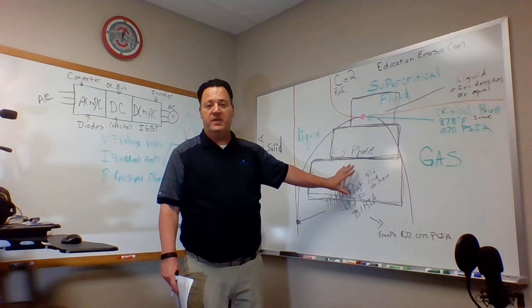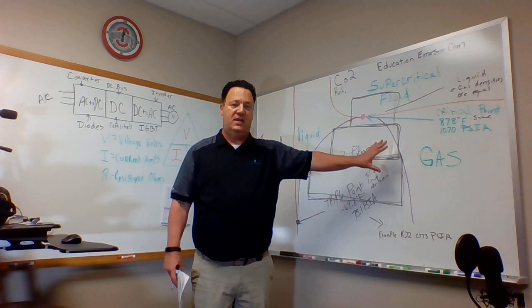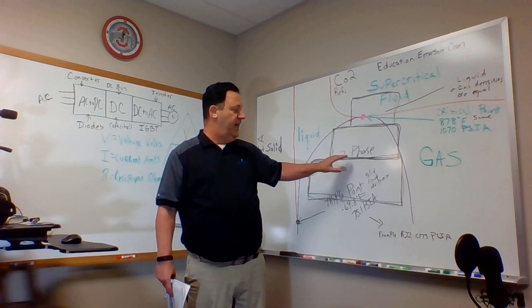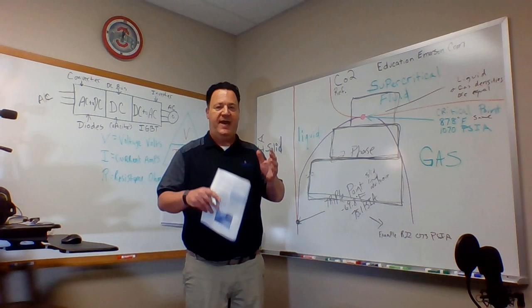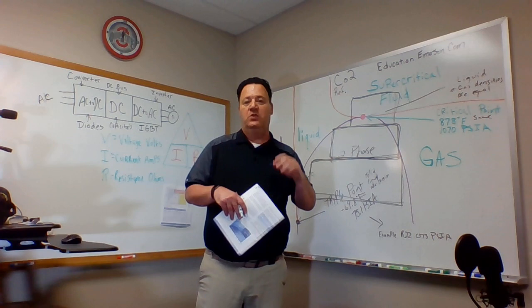The reason for that is it's actually tied in. It shares a suction line with the medium temperature rack on the CO2, and it is removing the heat on the low temperature via the medium temperature rack through a brazed plate heat exchanger acting as a condenser, and it's rejecting the heat there. It's transferring that, like you have in geothermals on the coax, if you understand geothermal. So we're removing that heat, and the medium rack is then taking it outside to the condenser and rejecting that heat as we normally would.